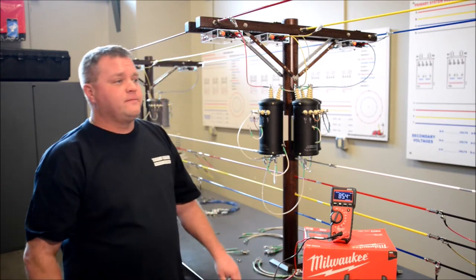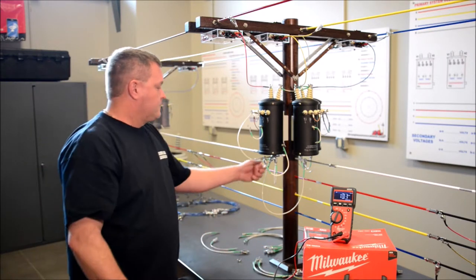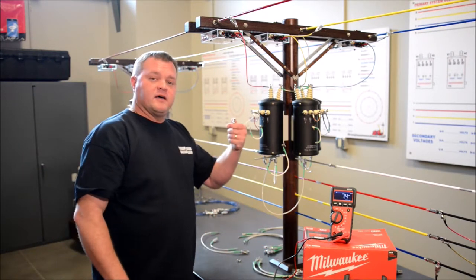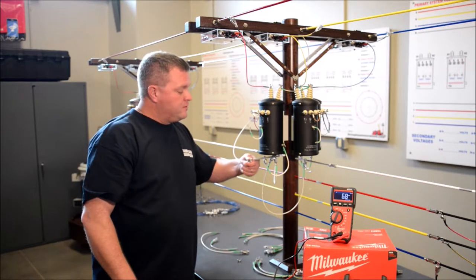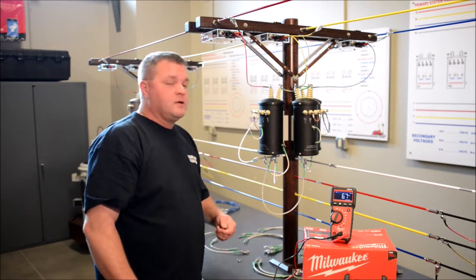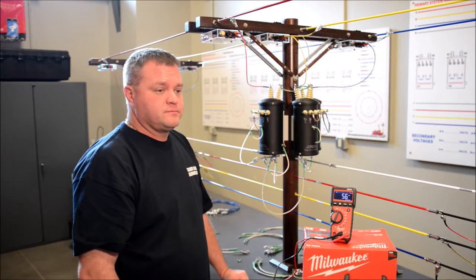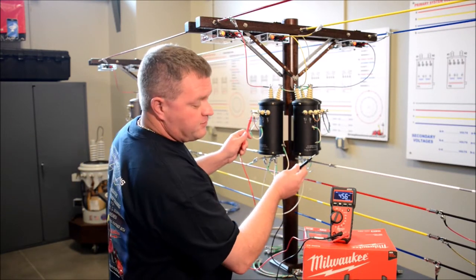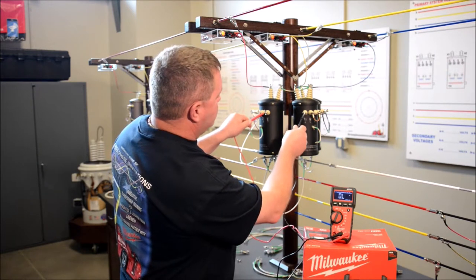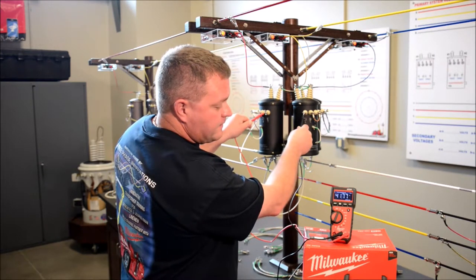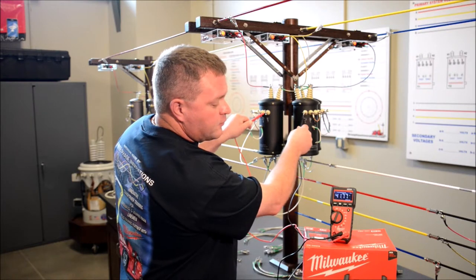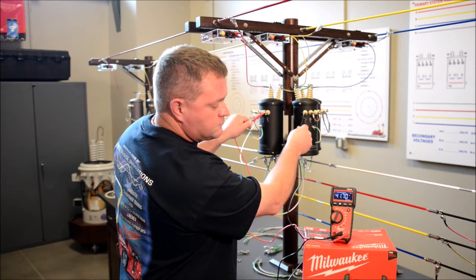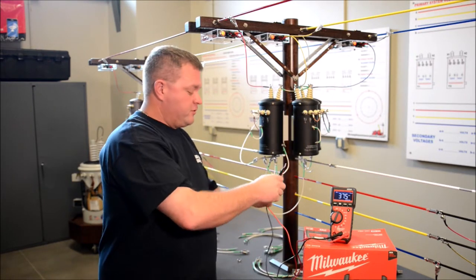Now Jason's going to de-energize it. I'm going to take the high side and we're going to temporarily ground it. Re-energize. Test point, X1 to X4. We're right at 41.7 volts. This will be considered good.